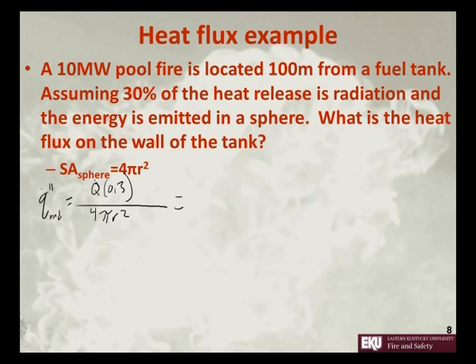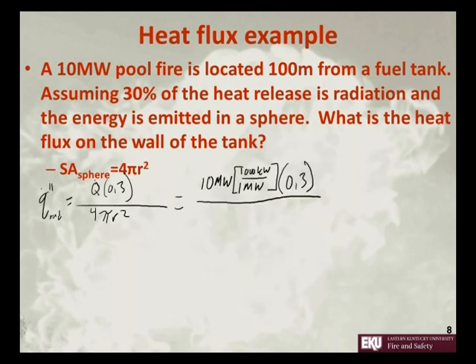This is equal to 10 megawatts, which 1 megawatt is 1,000 kilowatts, and we want to input our heat release rate in terms of kilowatts, times 0.3 divided by 4 pi times 100 squared.